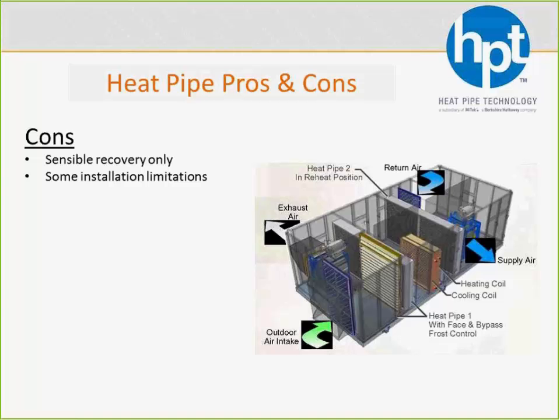And we do have some installation limitations, basically because we have to have the airstreams level to work year-round. If we had any kind of slope to the heat pipe, that liquid's only going to go down, which means we're only going to work when the warmer airstream is at the bottom. And there are some applications where that's perfectly fine, and we take advantage of that. But that is one of the limitations that we do have.